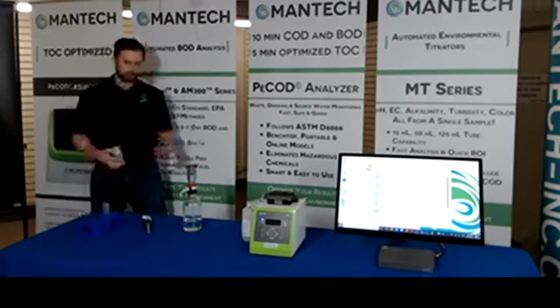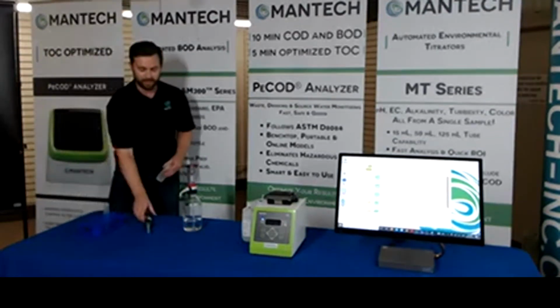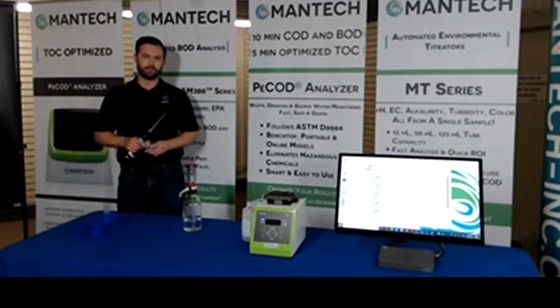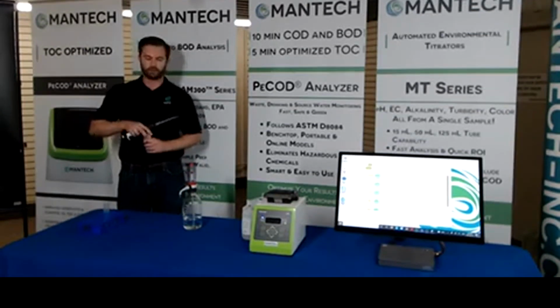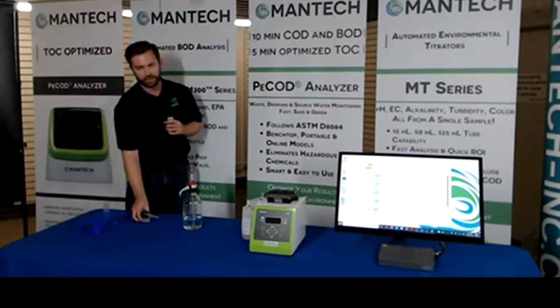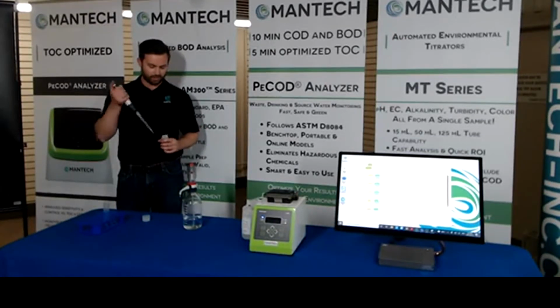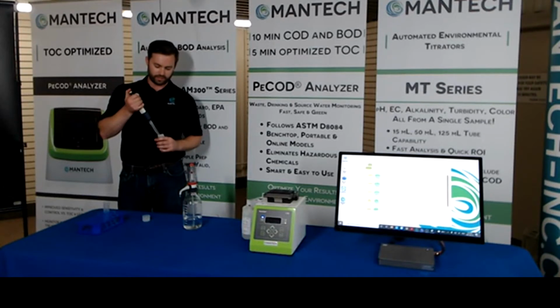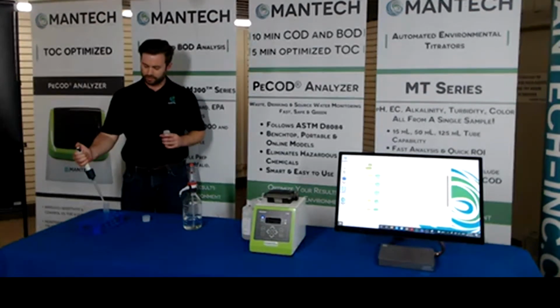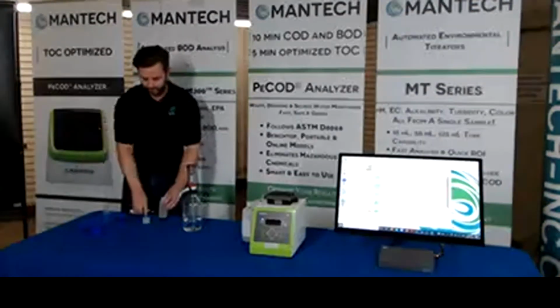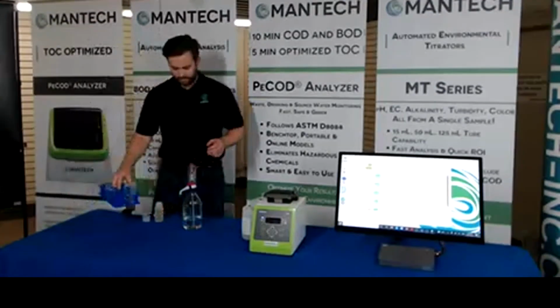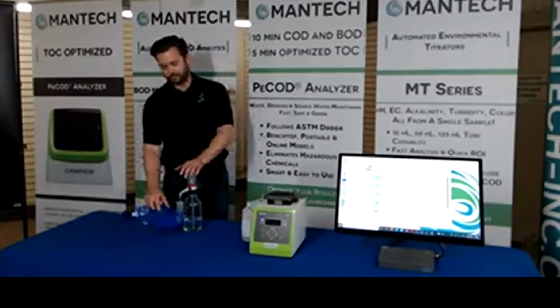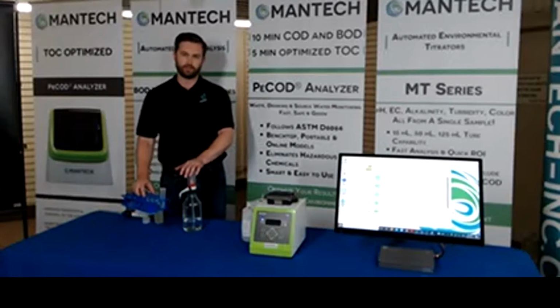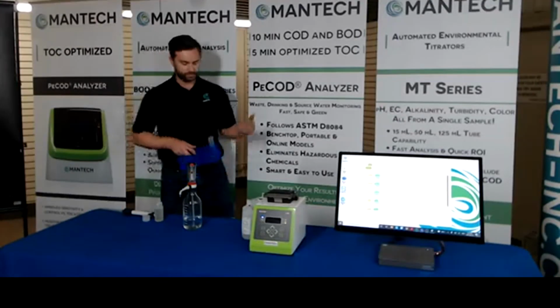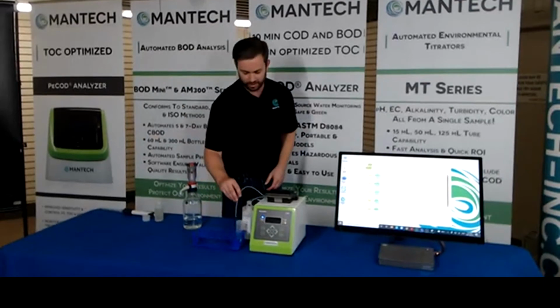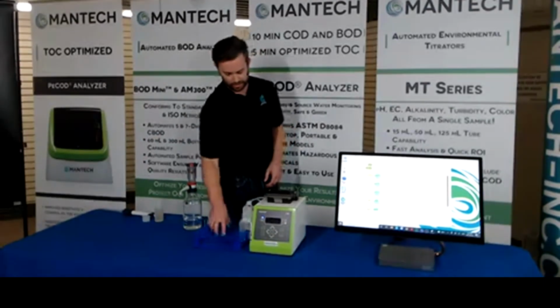I can just bring it right over, and first thing to do is pipette the sample into the tube that is going to be mixed with the salt reagent before it gets brought into the PeCOD. So I'm just going to go right there, bringing 10 milliliters of that sample into the tube, really nice and easy. I'm going to take my salt reagent, and we just use this bottle top dispenser to make it that much quicker and easier. Take your sample, prepare it in less than a minute, and bring it over to the PeCOD.